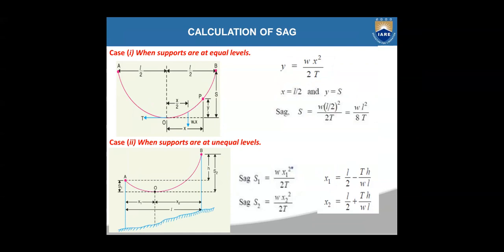When the supports are not at equal levels, you will have two sags S1 and S2. Those two sags are calculated using S1 = wx1²/2T and S2 = wx2²/2T. Here x1 is the distance from support A to the center of the conductor O, and x2 is the distance from support B to O. x1 and x2 can be calculated as x1 = L/2 − Th/wL and x2 = L/2 + Th/wL.